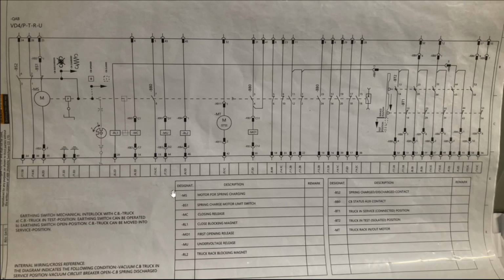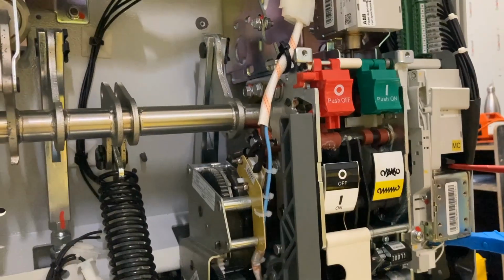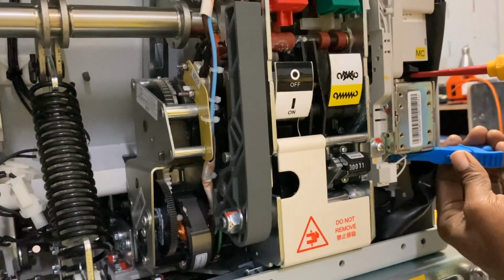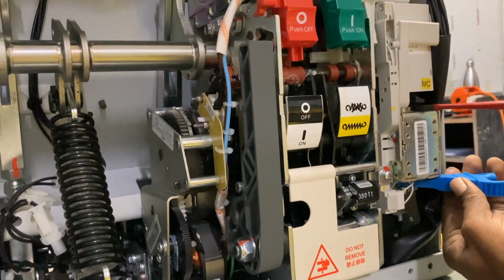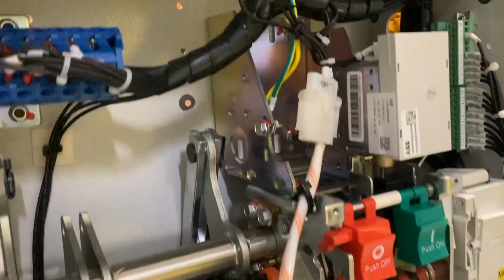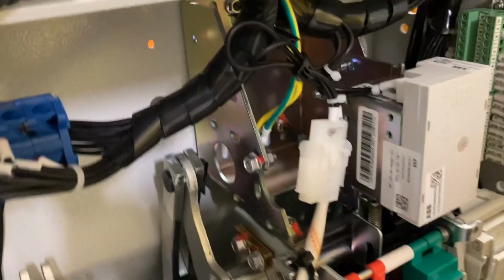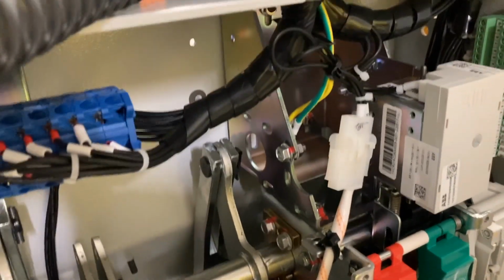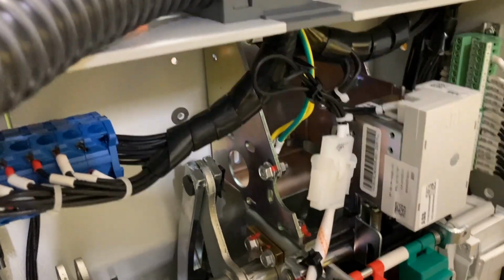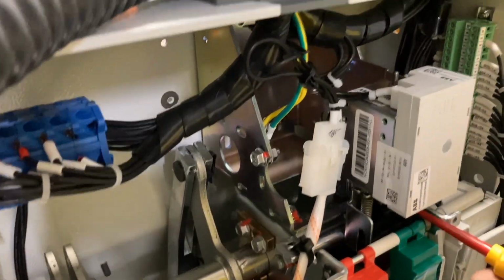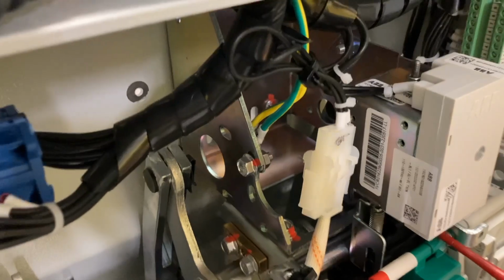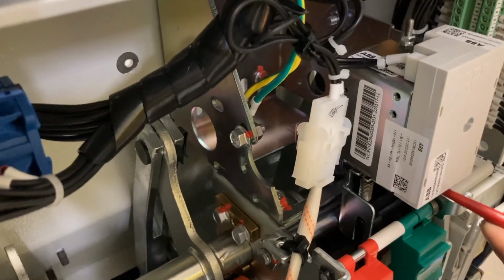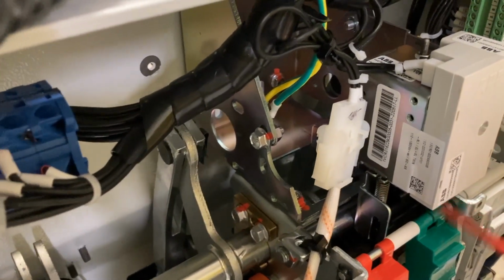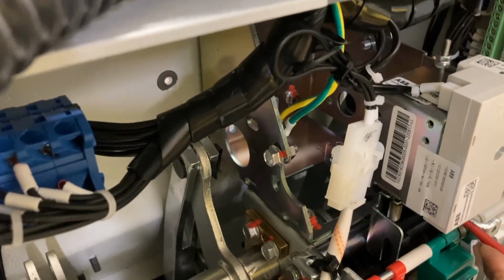Let's see the circuit breaker pin diagram and note down the terminals for closing, tripping and spring charge motor. Here I have one close blocking coil and one undervoltage release coil, which I am going to bypass manually. See, when I press below, the screw pops out. So I am going to bypass it manually by using a crocodile clip.